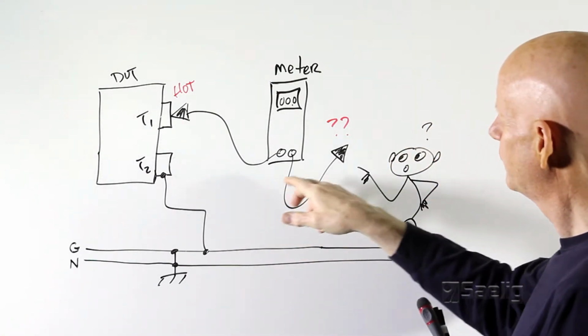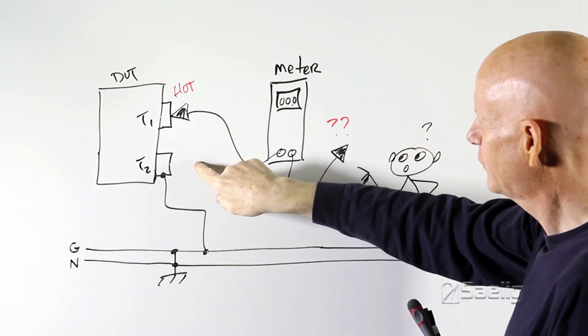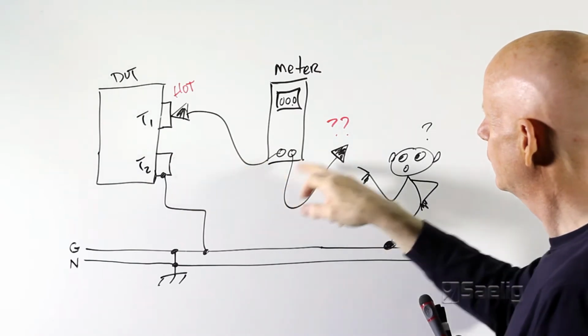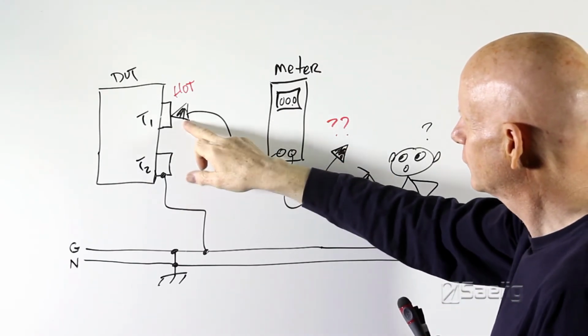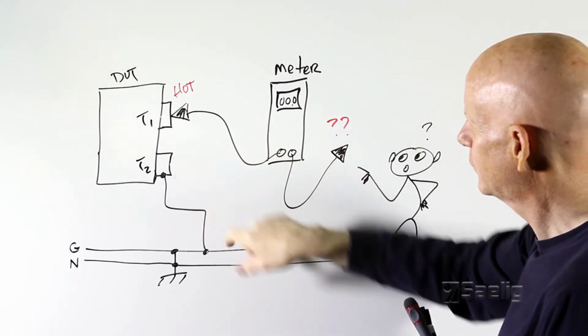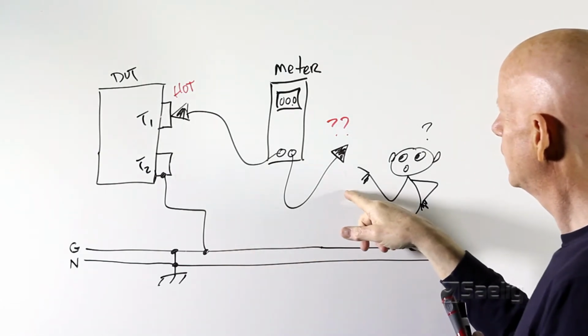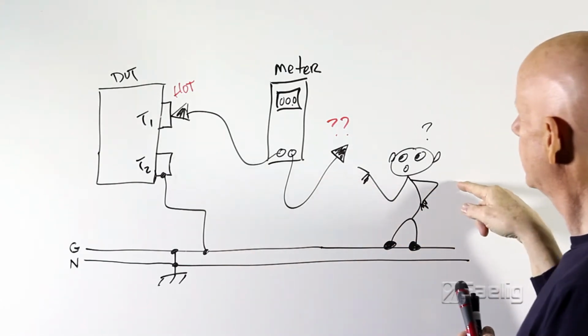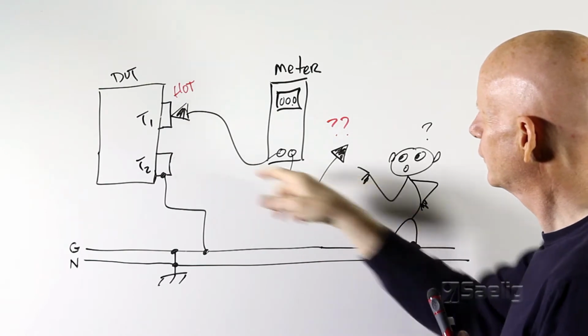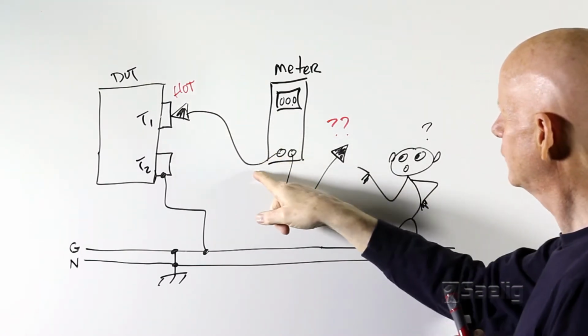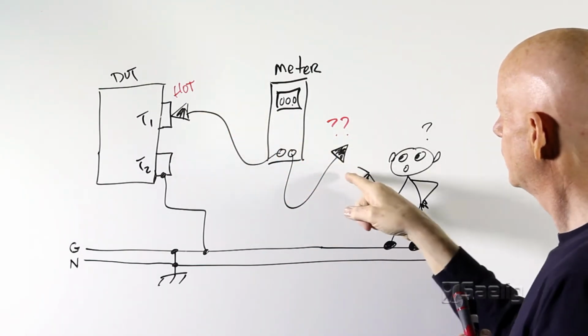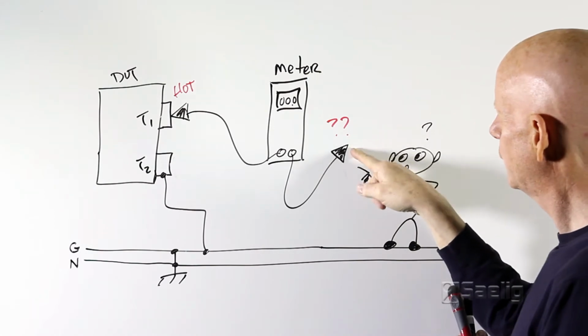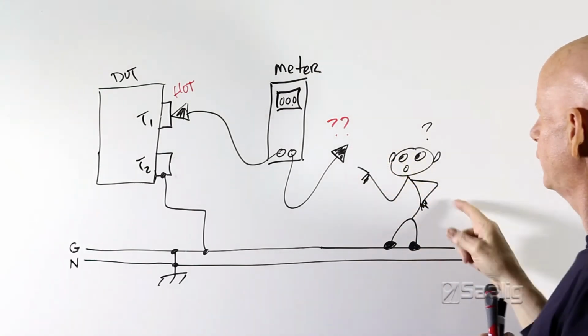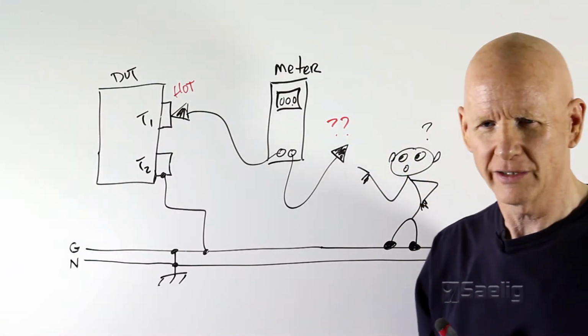The other thing is, be careful how you unattach things after you've already attached them. We just used this meter here to measure from T1 to T2, and T2 was ground. So that was fine, except that the fella here disconnected the ground first and left the high side still connected. Through the meter, we're going to find something very close to the high side voltage right here, and if he's grounded, he can get a tickle out of that.